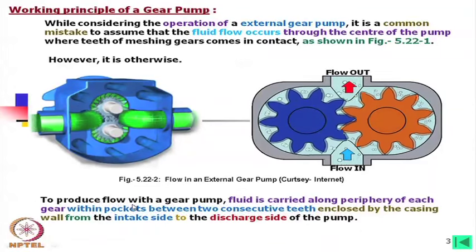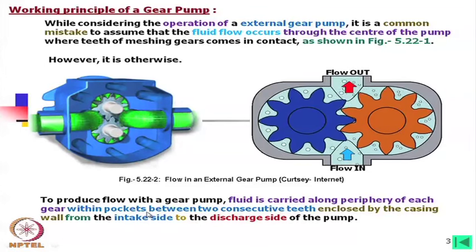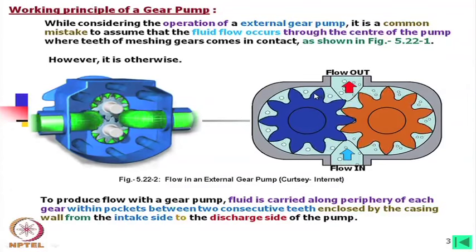To produce flow, fluid in a gear pump is carried along the periphery of each gear within pockets between two consecutive teeth enclosed by the casing wall, from the intake side to the discharge side of the pump. Within one revolution, the number of pockets is exactly double the number of gear teeth — so one may consider that as the number of chambers in a gear pump. With an increase in number of chambers, the ripple actually reduces.